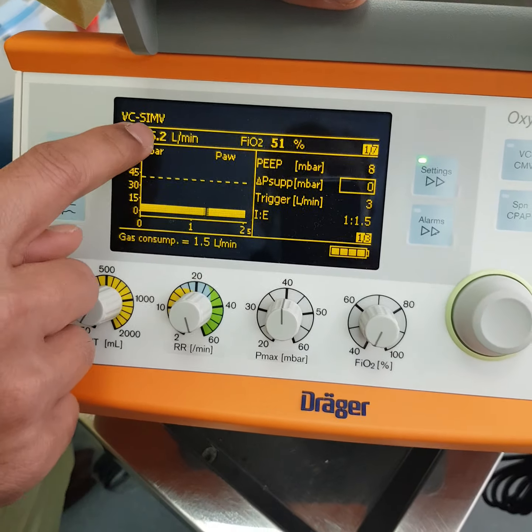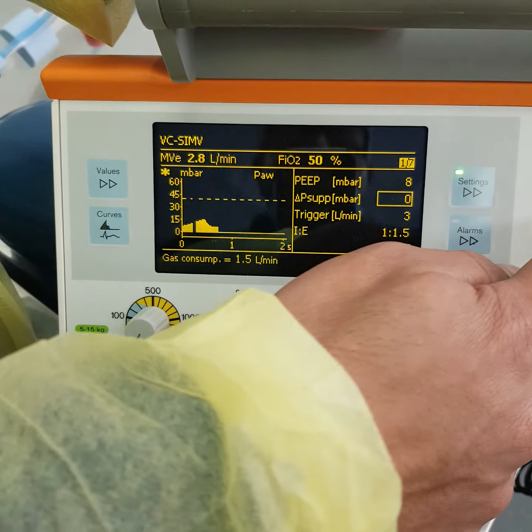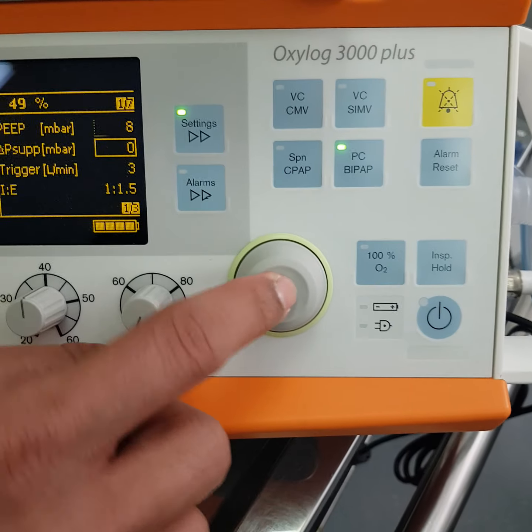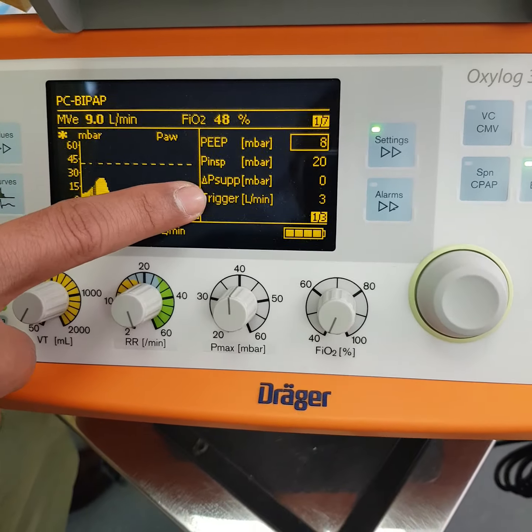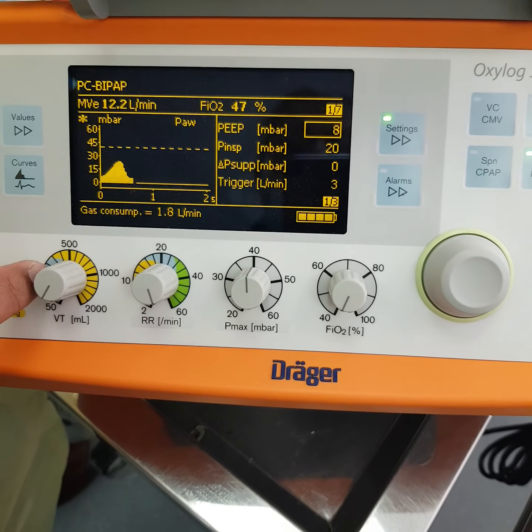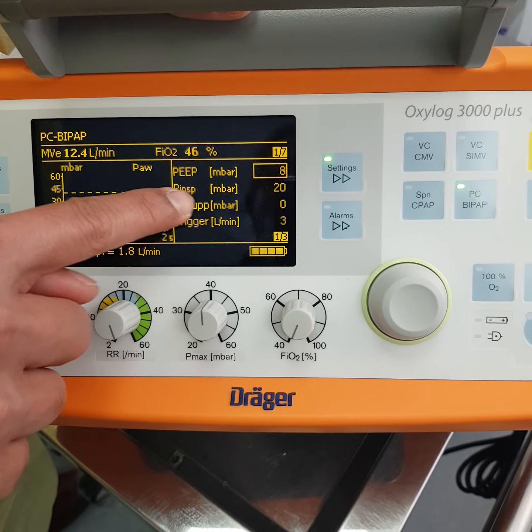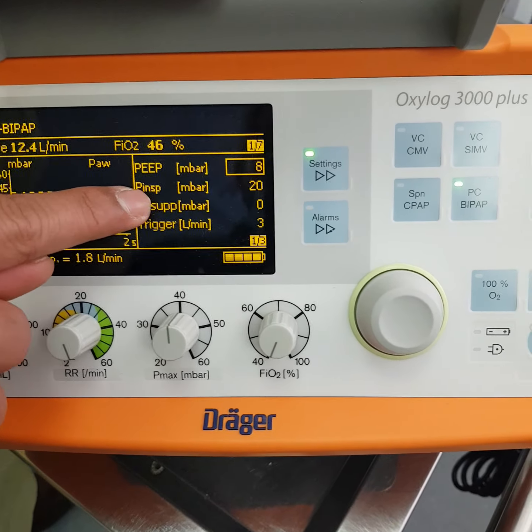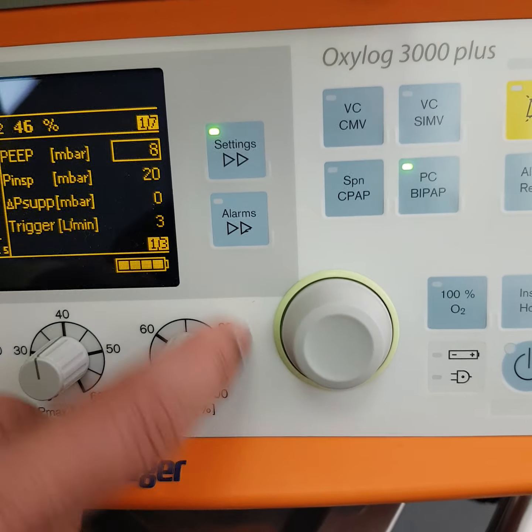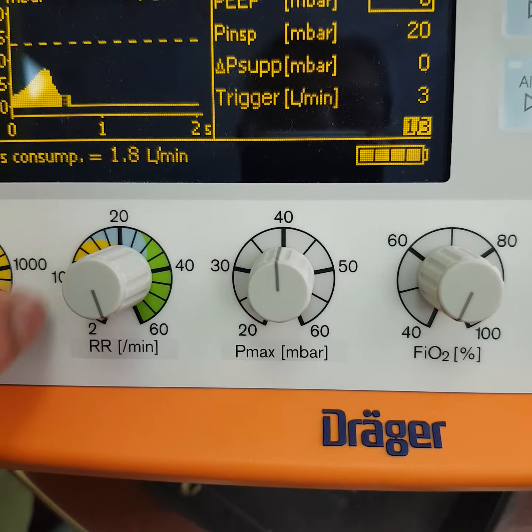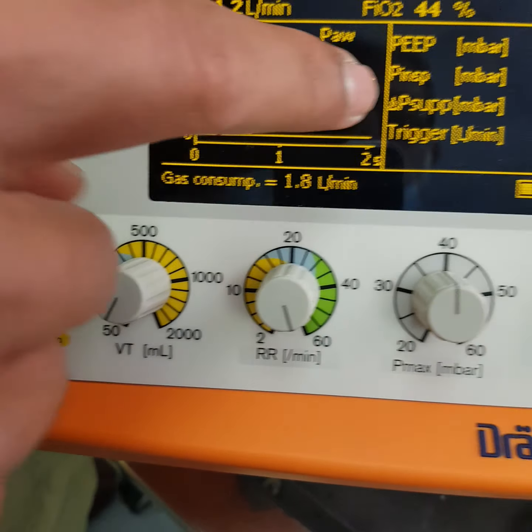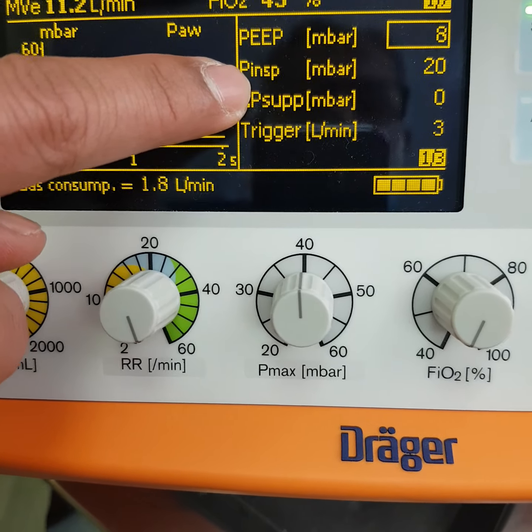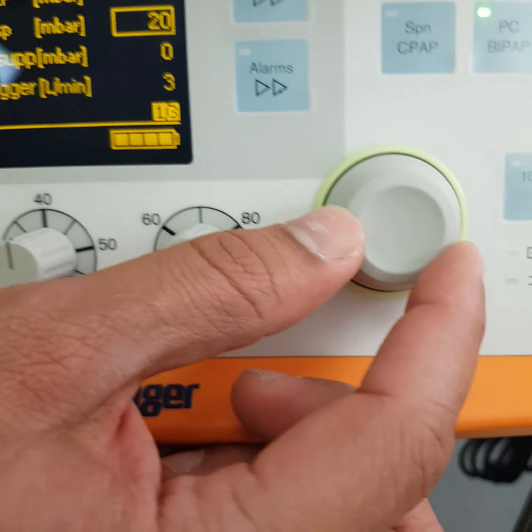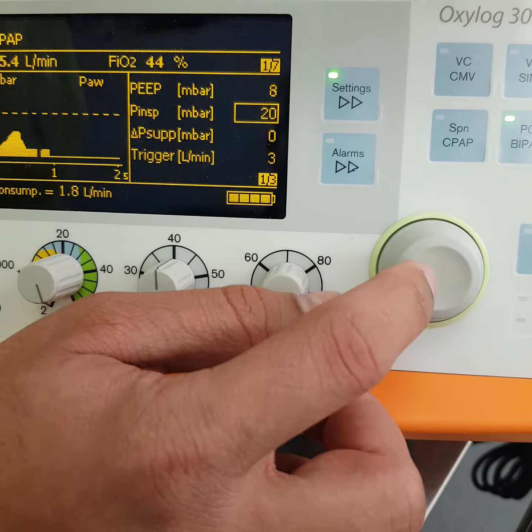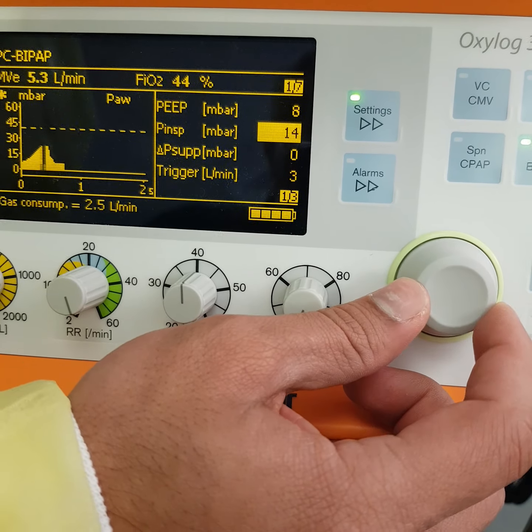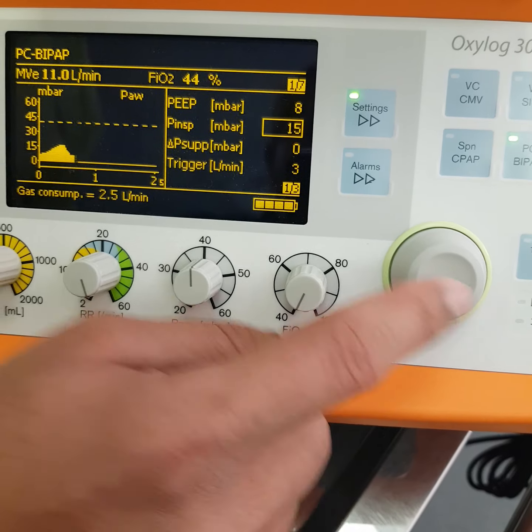Since we are on volume control SIMV, you can activate pressure support as well. If you are on pressure control BiPAP, it can have pressure support as well, but it will deactivate the tidal volume settings, and it will activate only the inspiratory pressure parameter, which is inside the screen. So outside you will have only these three parameters, and the tidal volume parameter will be deactivated. So your tidal volume will be according to the inspiratory pressure that you set up here.